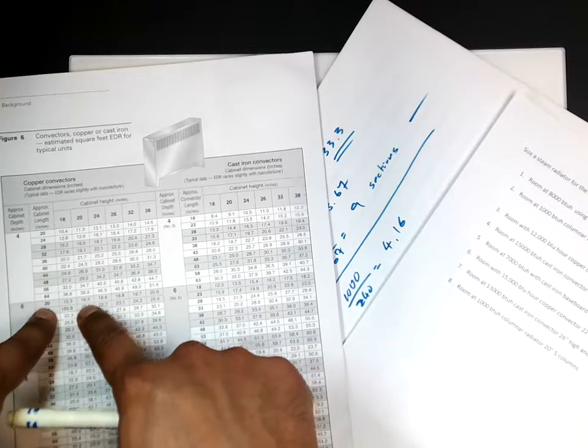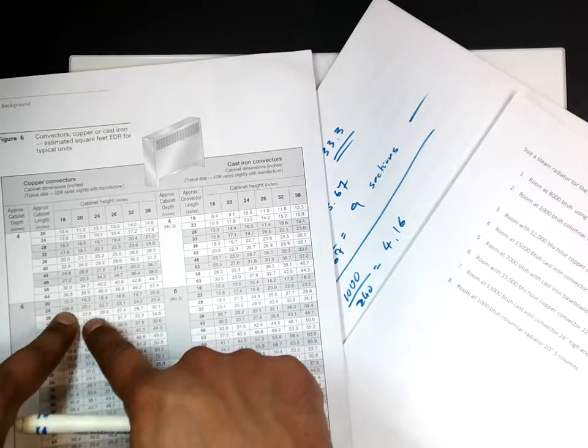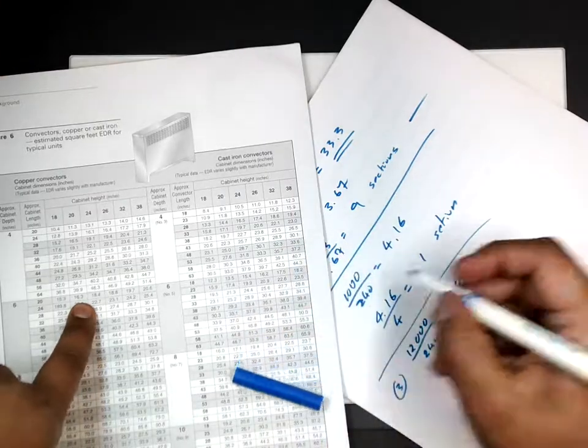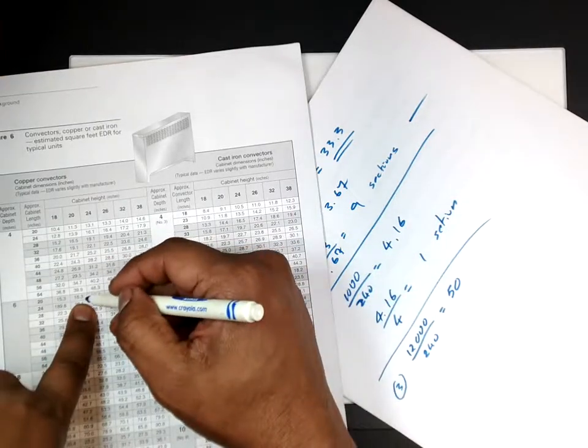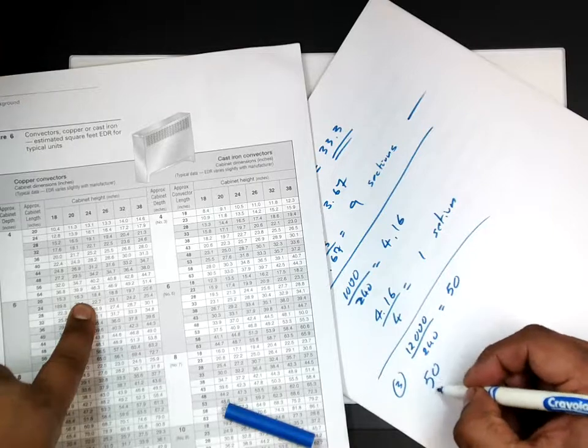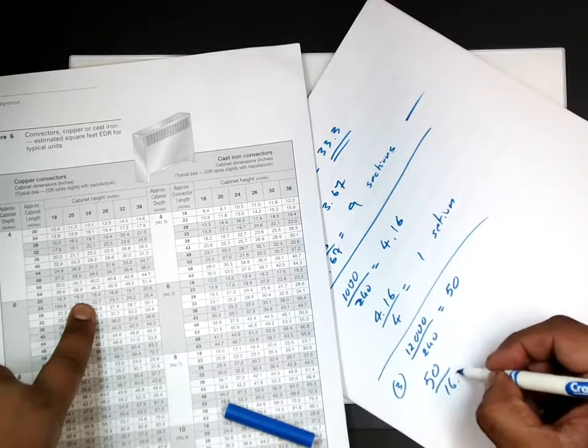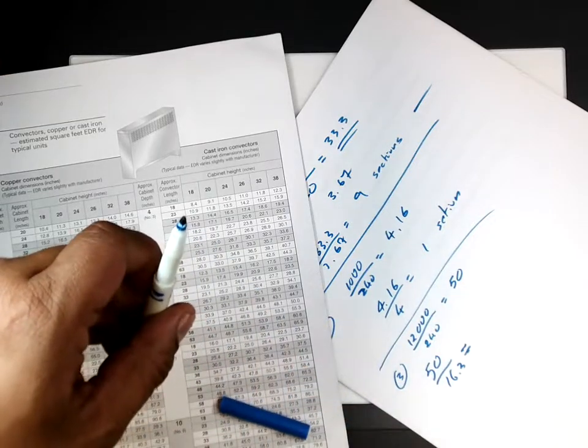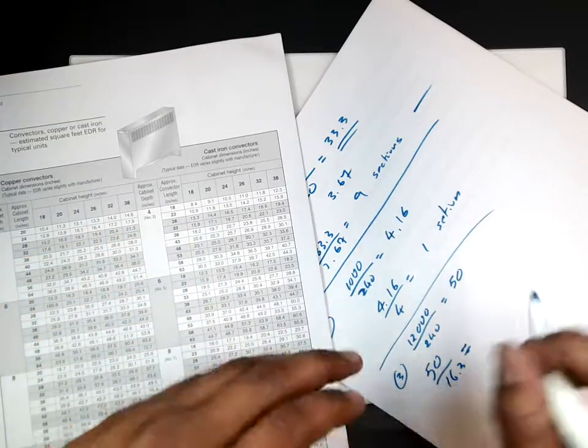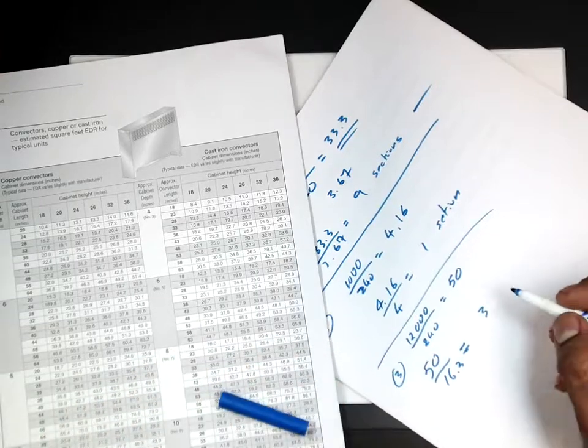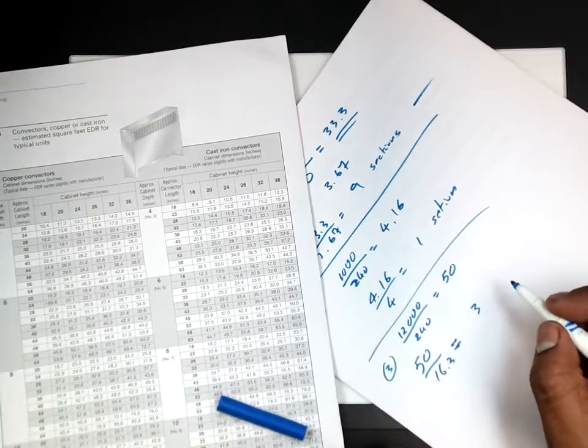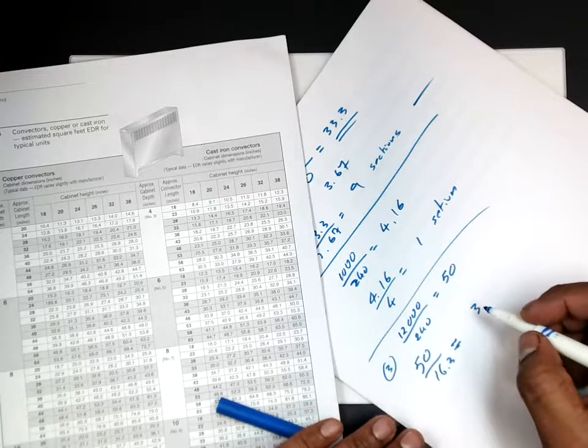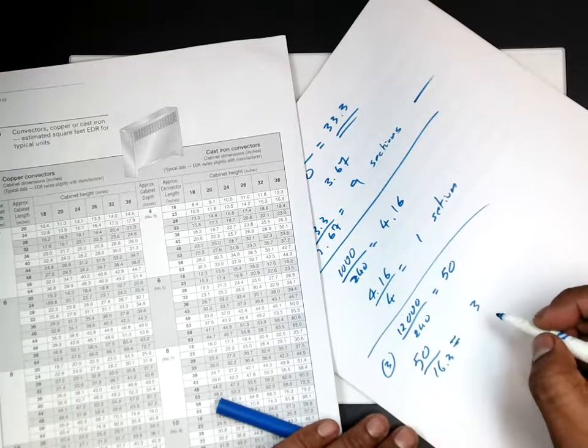Again, I'll get a smaller one because it's going to be cheaper. You can go higher, it doesn't matter. So I'm going to pick the first one and from here, if you can see the EDR is 16.3. 50 over 16.3. That will give me three sections. That's the inches. That's the EDR. I'm going to get three of those, three sections.